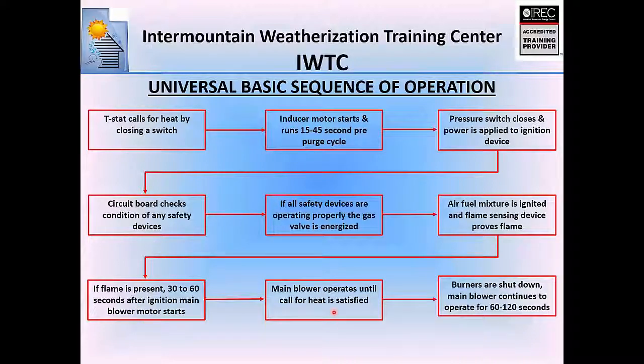The main blower operates until the call for heat is satisfied. Burners are shut down when the call for heat is satisfied, and the main blower continues to operate for 60 to 120 seconds. So this is the basic sequence of operation. There are some other furnaces that have more to it than this, but again, this is Furnace 101, so we're going to start you with the basics.